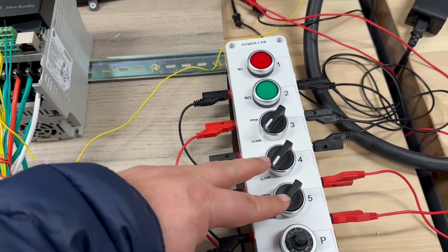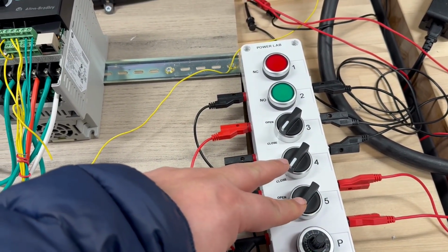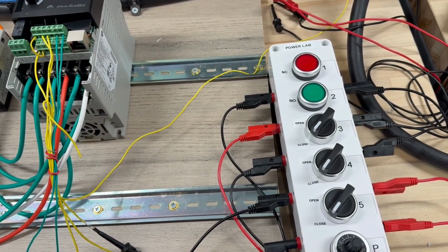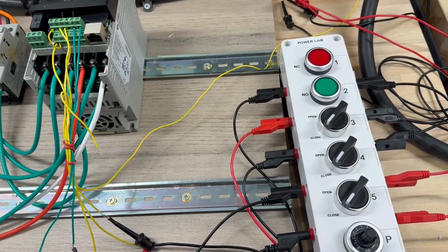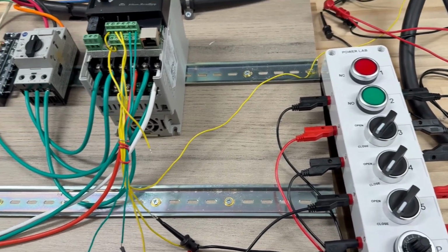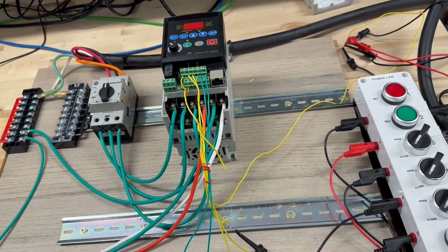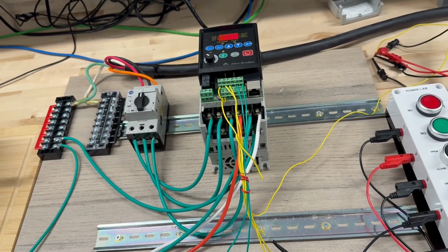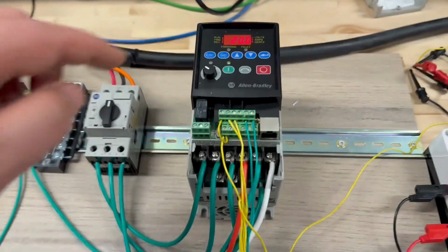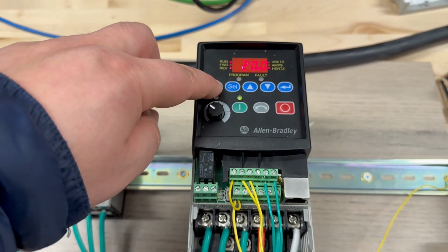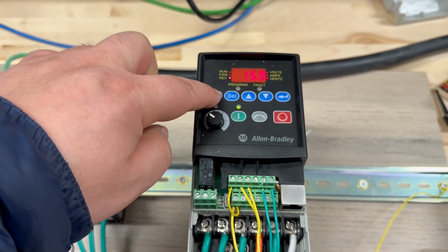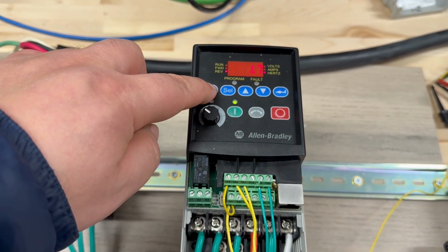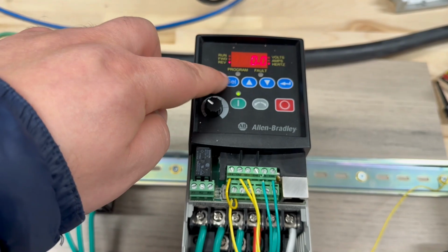As you can see, with these two digital inputs, 5 and 6, you could set any frequency that you want. As you see, 0, 5, 10, 20 are the defaults. We could change them to any frequency that we want. Let me try one so you can see how it works. Let me stop it. I'm going to start with A70, which gives us 0 by default.